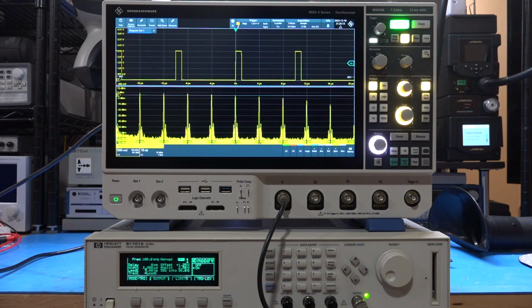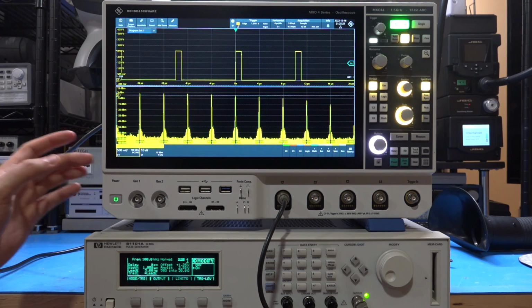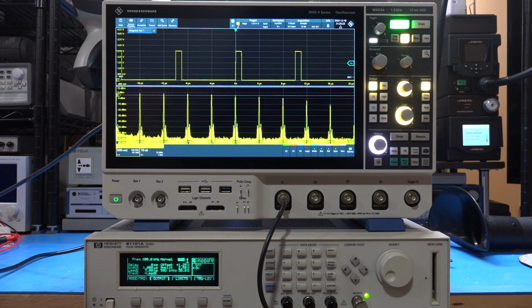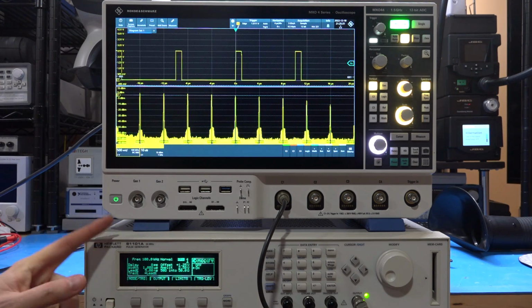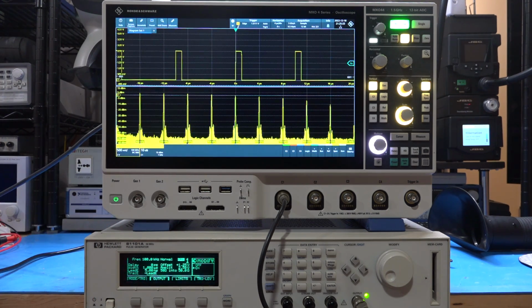Now this thing is supposed to be able to put 10 volts into 50 ohm and 20 volts into essentially high impedance. So I just want to verify that as well. I'm not going to put 10 volts into the 50 ohm of this instrument, because I think that might be over what it can take. I have to double check. But just to be on the safe side, we can put this into high impedance mode and put the maximum signal it can do and the maximum frequency. I also want to measure the frequency accuracy of this as a last test to make sure everything is okay. So let's set that up.